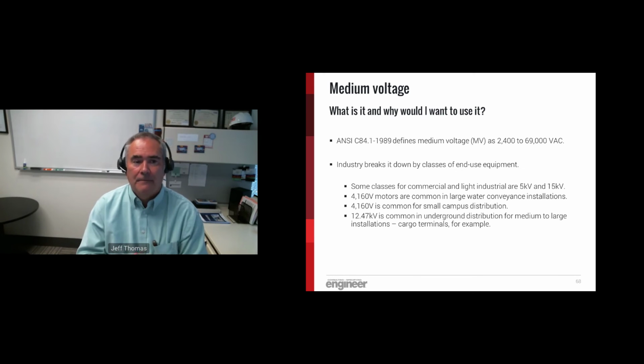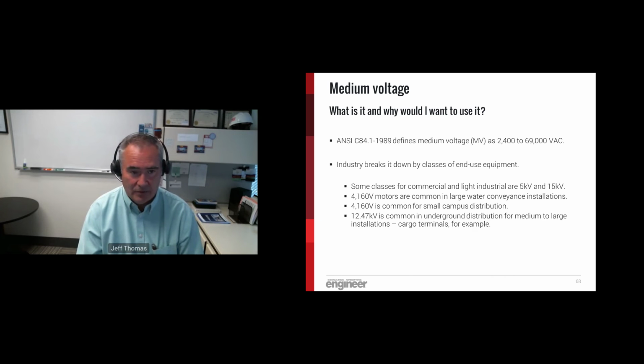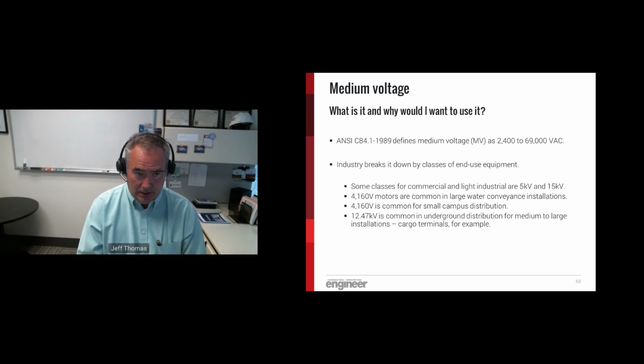So real quickly, let's talk about medium voltage. We talked about I squared R losses in conductors, and one way to get those down is to get the voltage even higher. So medium voltage, what is it and why would I want to use it? Here we've got an ANSI standard. The ANSI standard defines medium voltage as 2,400 to 69,000 volts. Another definition specifies medium voltage as 1,000 to 35,000 volts. So the answer to the question, what's medium voltage, is it depends on who you ask.